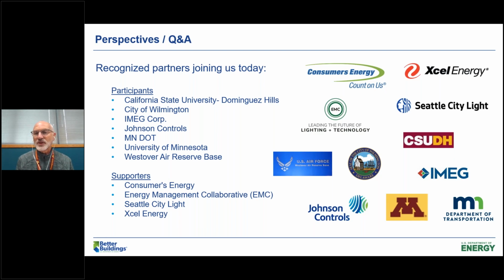So when the room is empty, even though it's the middle of the day, we could allow our temperatures to drift a little bit, and I think that was key to our success. The lighting, having the lights turn on and off based on occupancy, I think most people get that, it's just a matter of implementing it in as many spaces as you can. The photocell was also another feature where, if there's already plenty of daylight, the lights would quickly dim.